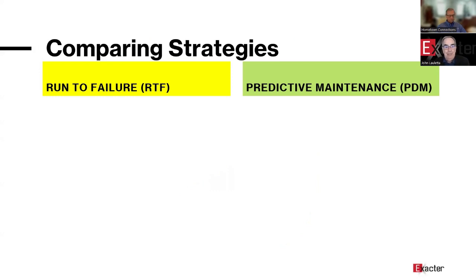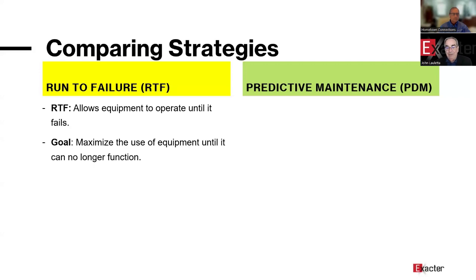Most utilities will tell you that they have a run to failure strategy when it comes to electric grid equipment. An outage occurs, resources are mustered, extraordinary effort is put out, and the circuit is brought back into compliance and operation. There's problems with that, though. You're allowing the piece of equipment to fail, the transformer to catch fire, the insulator that's cracked to flash over, whatever it is, you're allowing that to happen. And when it happens, then you have to react.